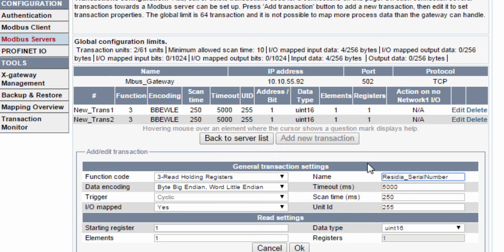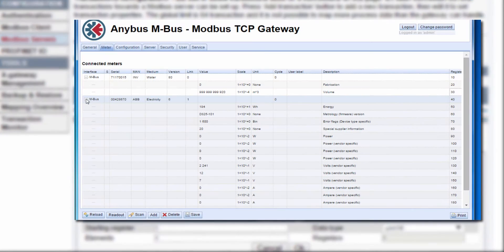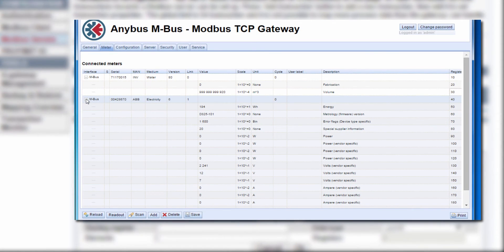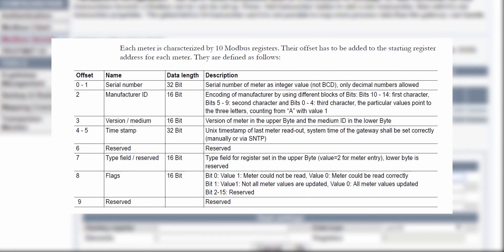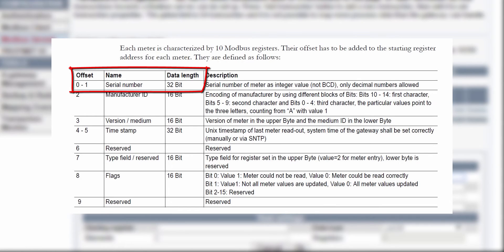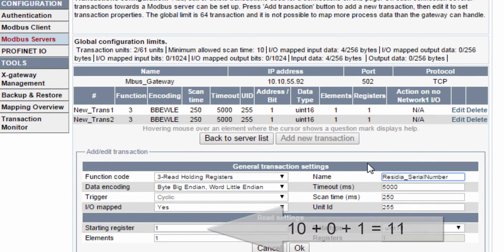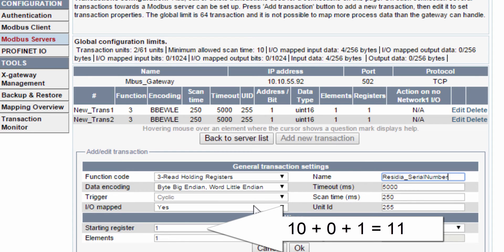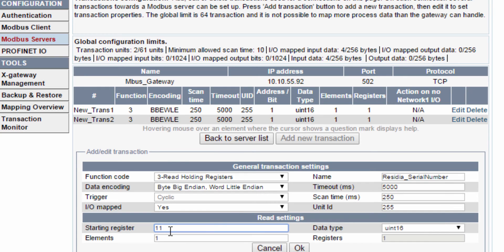Now, when it comes to allocating the registers from the MBUS gateway to the X-Gateway Modbus TCP, we need to do some calculating. In the Configuration Manager for the MBUS gateway, we could see that the registers for the water meter starts at register 10. If we look at the manual for the MBUS gateway, I can see that the serial number for a meter starts at 0 and goes to 1. That means that I will have a starting register at 10 plus 0 plus 1 since I have an offset of 1 between the two gateways. The number of elements is 2 since the serial number is a 32-bit value.